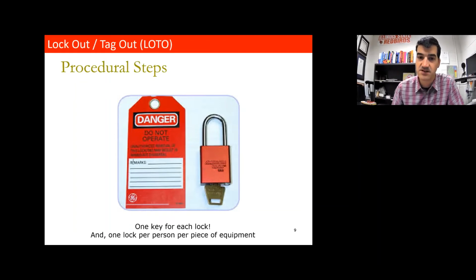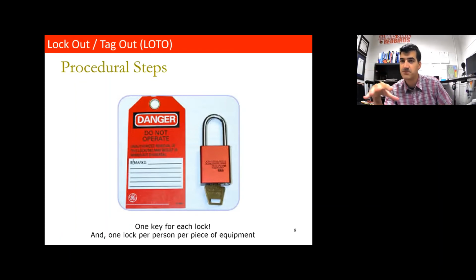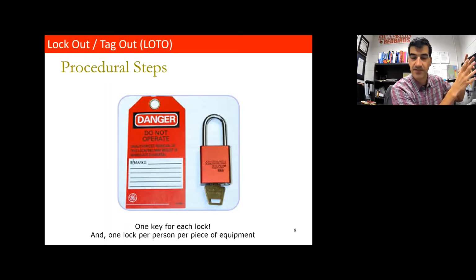Hope that's clear, it's very important: one key for each lock, one lock per person, per component -- meaning the component that's de-energizing that piece of equipment, not just the piece of equipment itself. One lock per person per component that's de-energized in order to de-energize the equipment. Let me know if that's not clear.